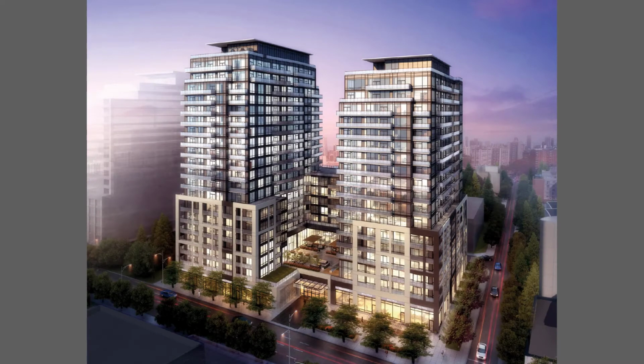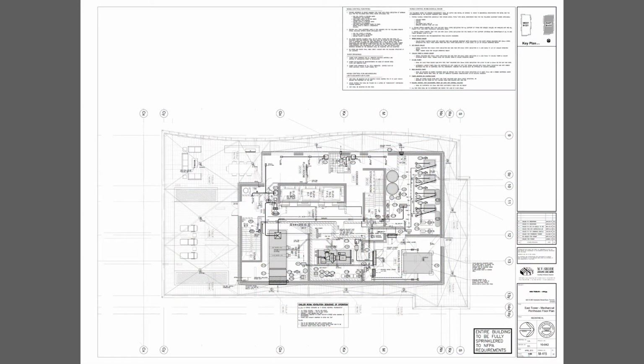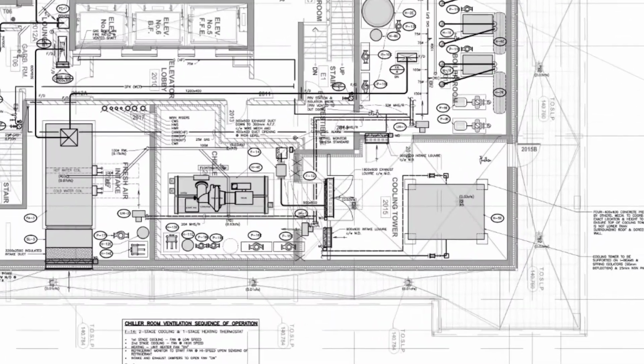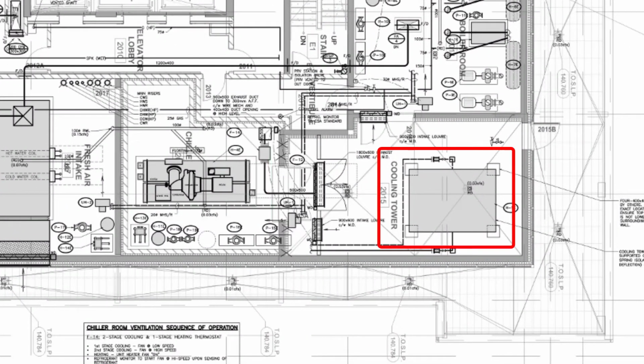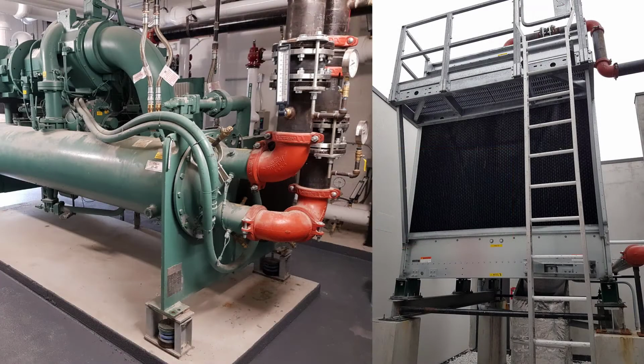We're going to go to another project now to look at some installations on other equipment and where control rods were used. This project was done in 2015 and is called the Axiom Condominiums, which is also located in downtown Toronto. Here shown on the East Tower mechanical penthouse floor plan is a water-cooled chiller and its associated cooling tower. We're going to go look at both of these pieces of equipment and focus on the expansion joint flexible connectors complete with control rods used on their pipe connections.